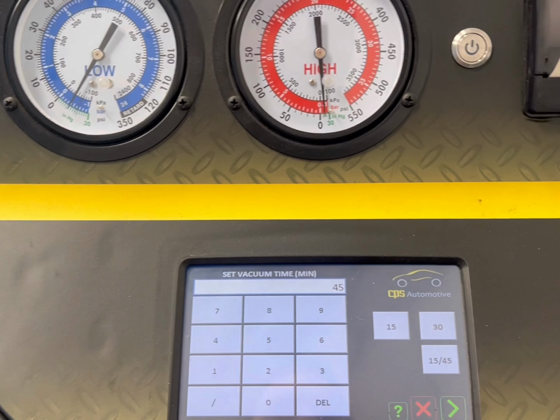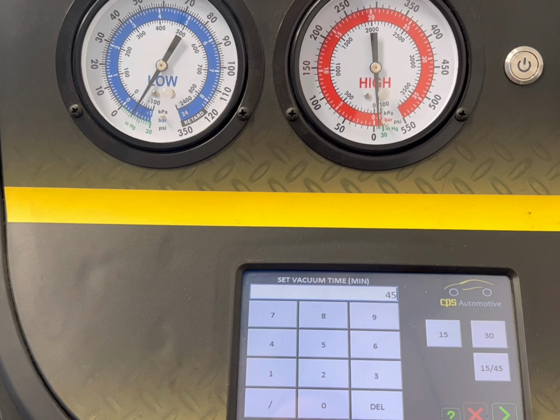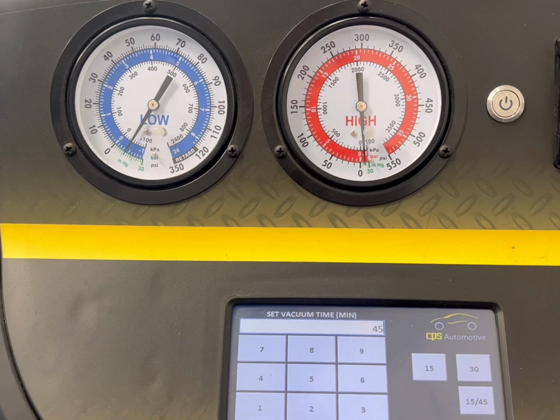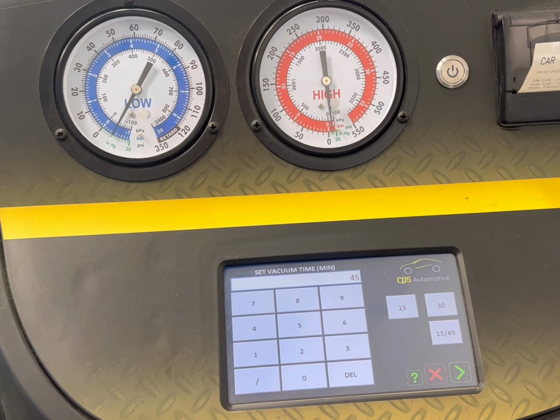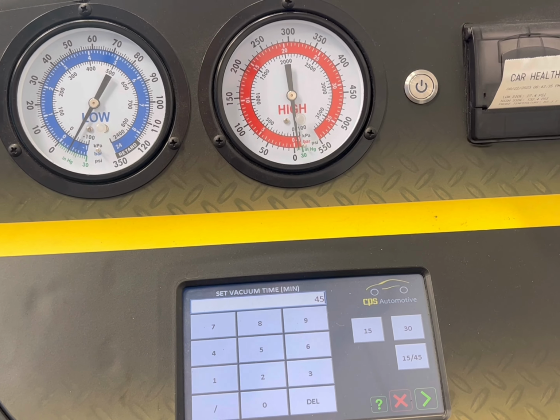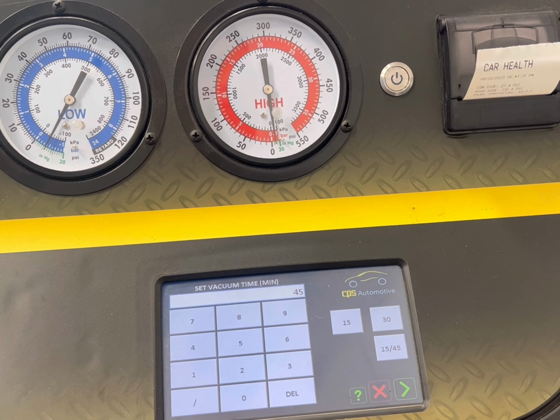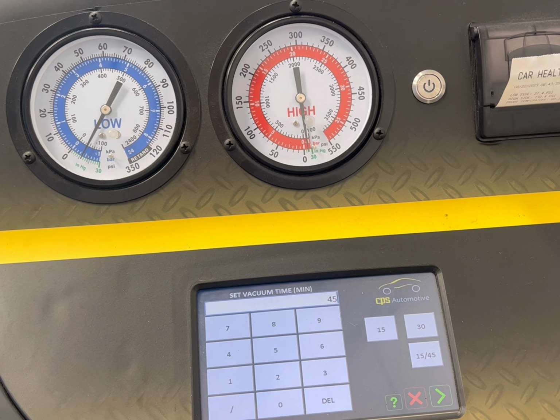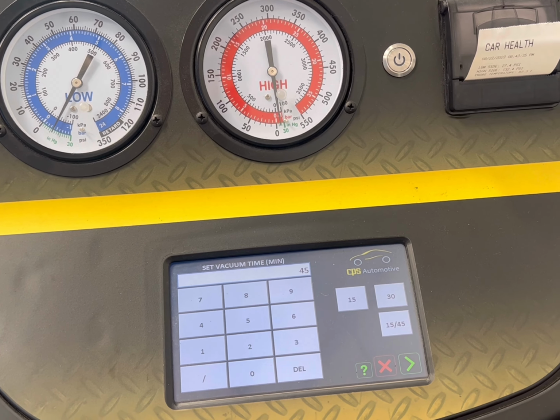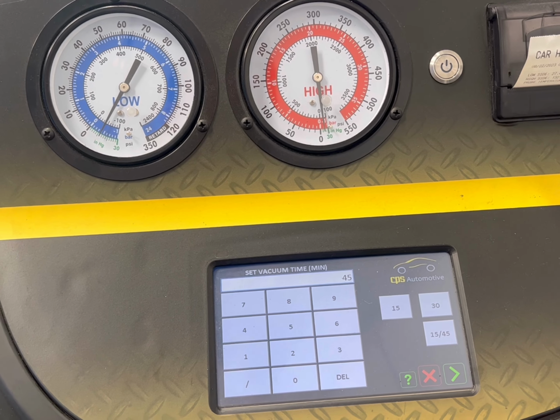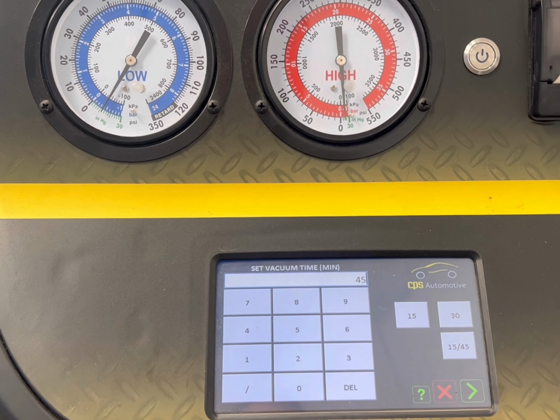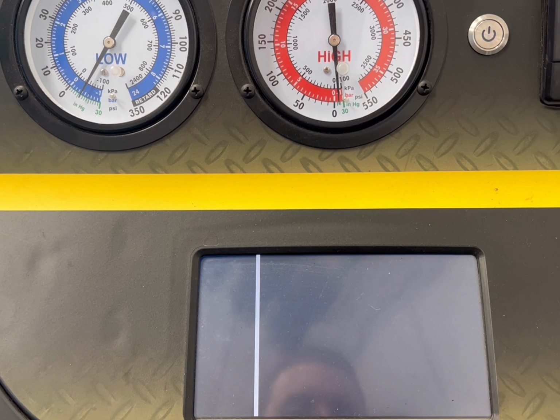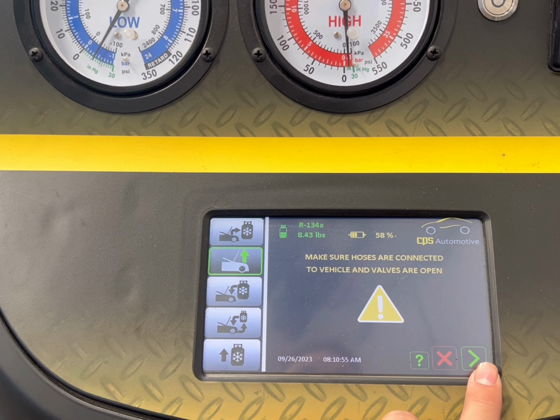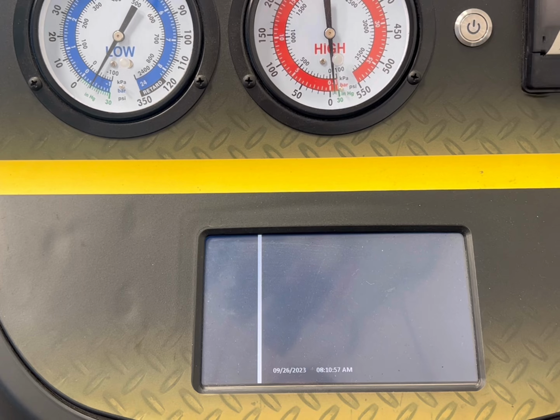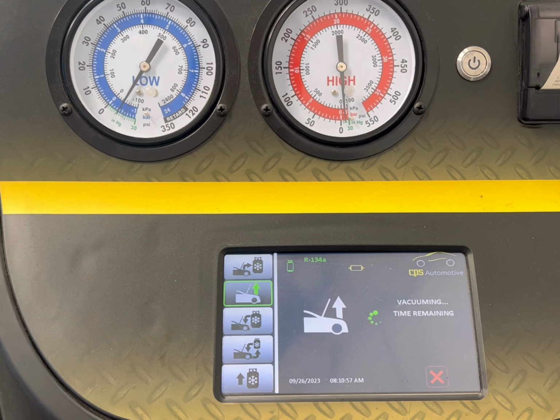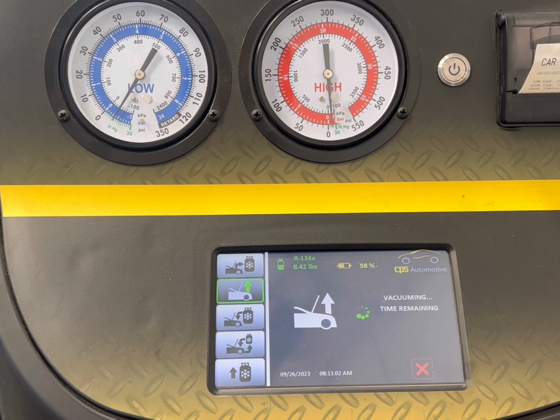Customers are paying for a good quality job, and an extra 15 minutes isn't that much more time. The reason you do a vacuum is you're taking out any excessive Freon, but most importantly you're taking out moisture. As it drops in pressure and goes into a vacuum, the moisture starts to evaporate and boil off. So that's what we're going to attempt right now. Go next, make sure the hoses are connected, which they are, and walk away for 45 minutes. It'll start beeping when it's done.